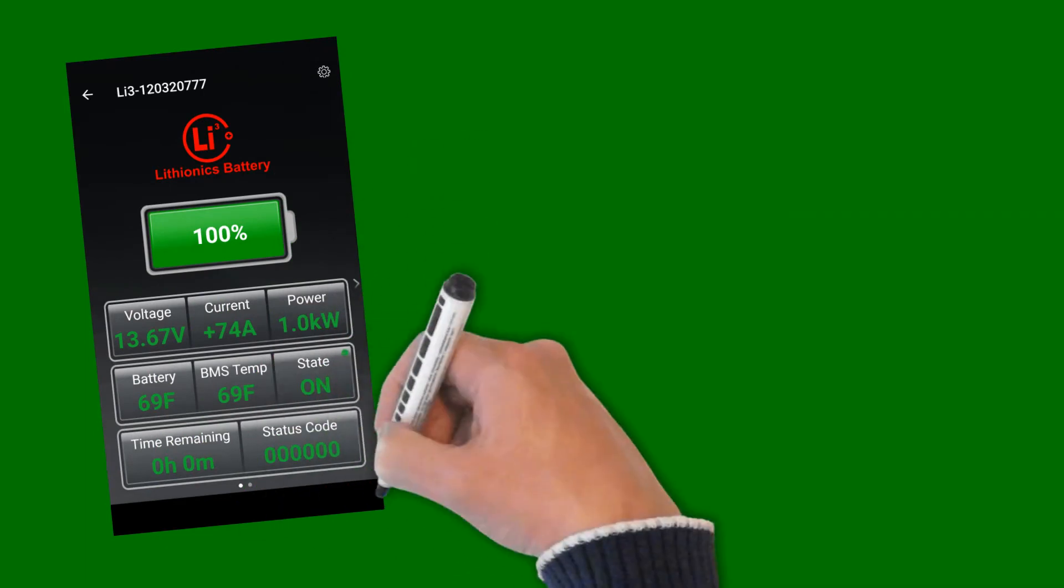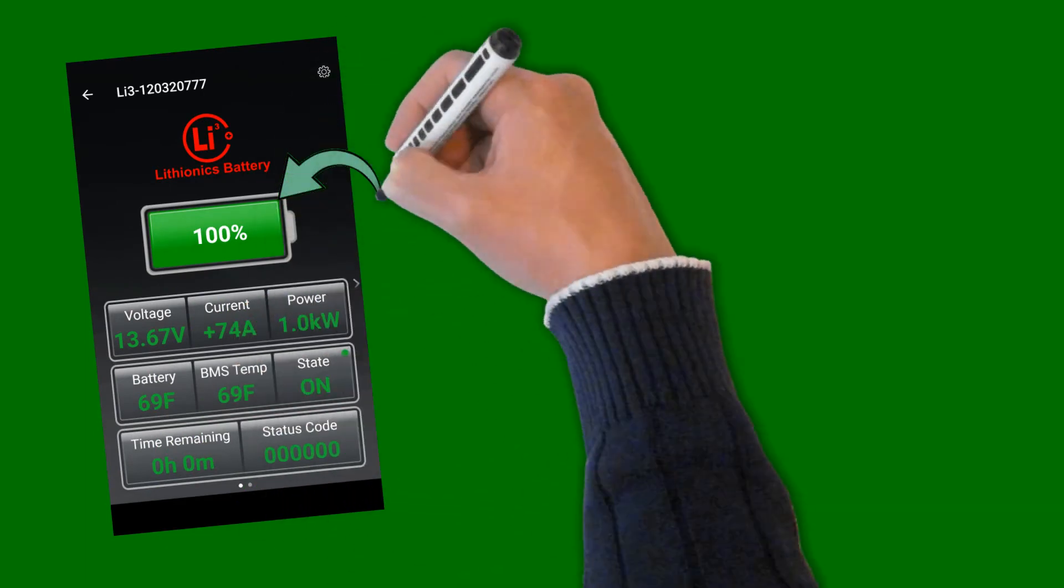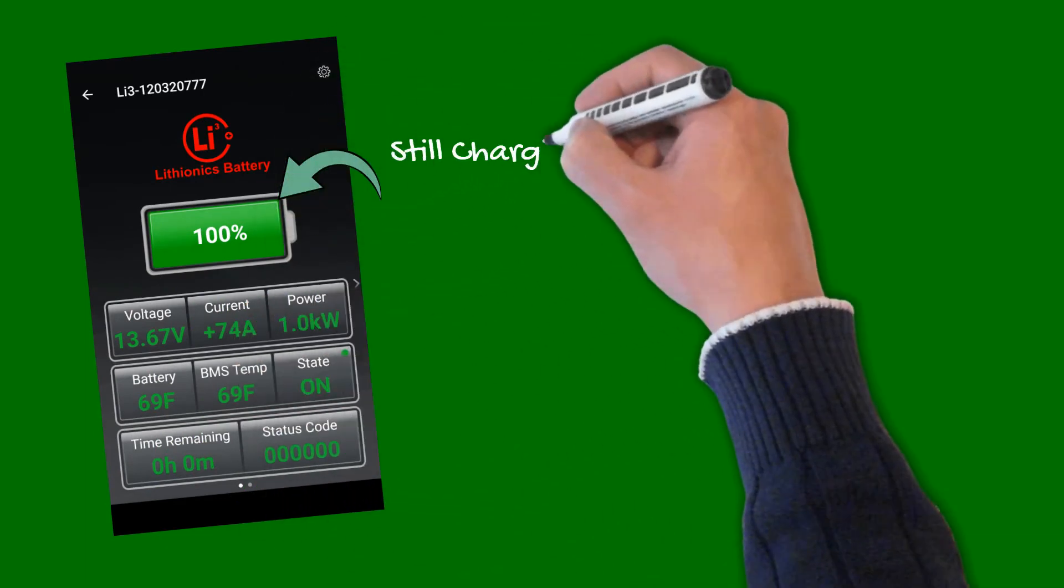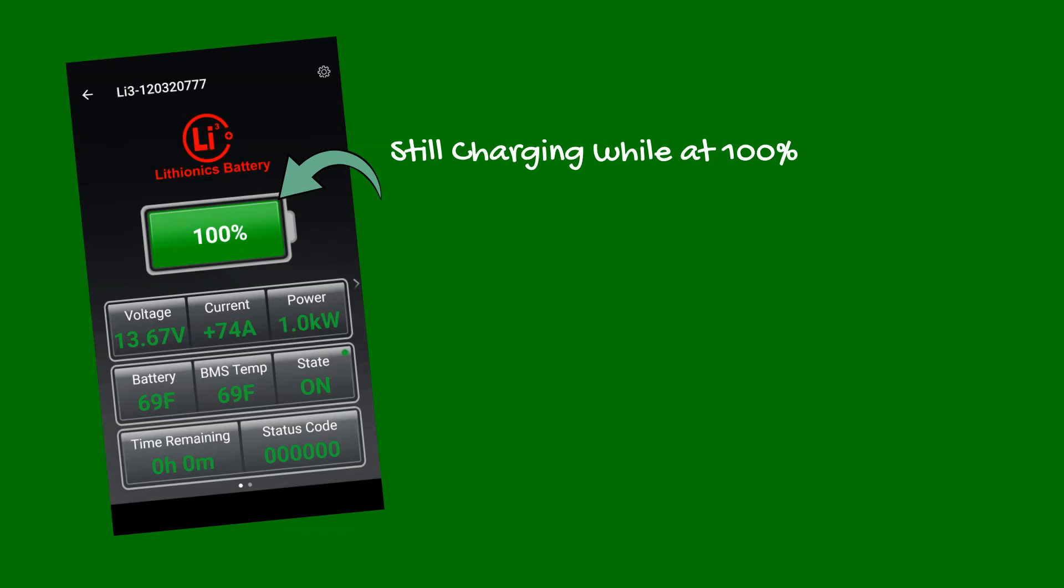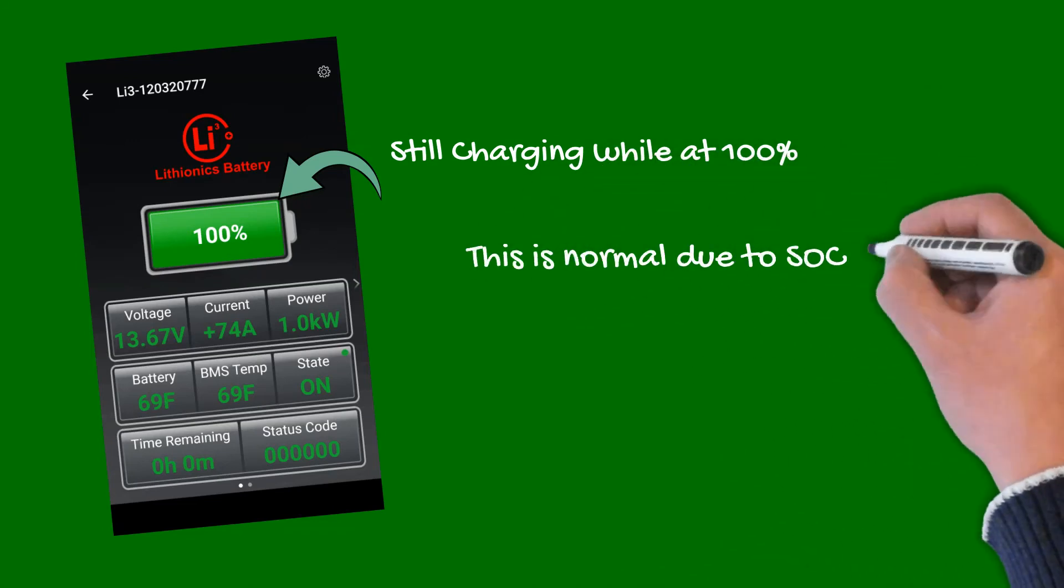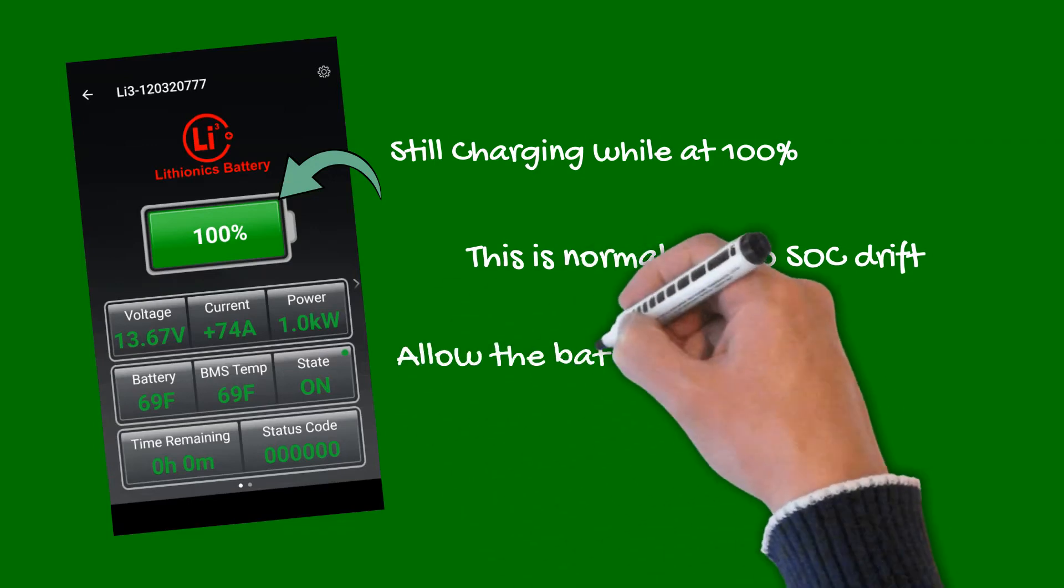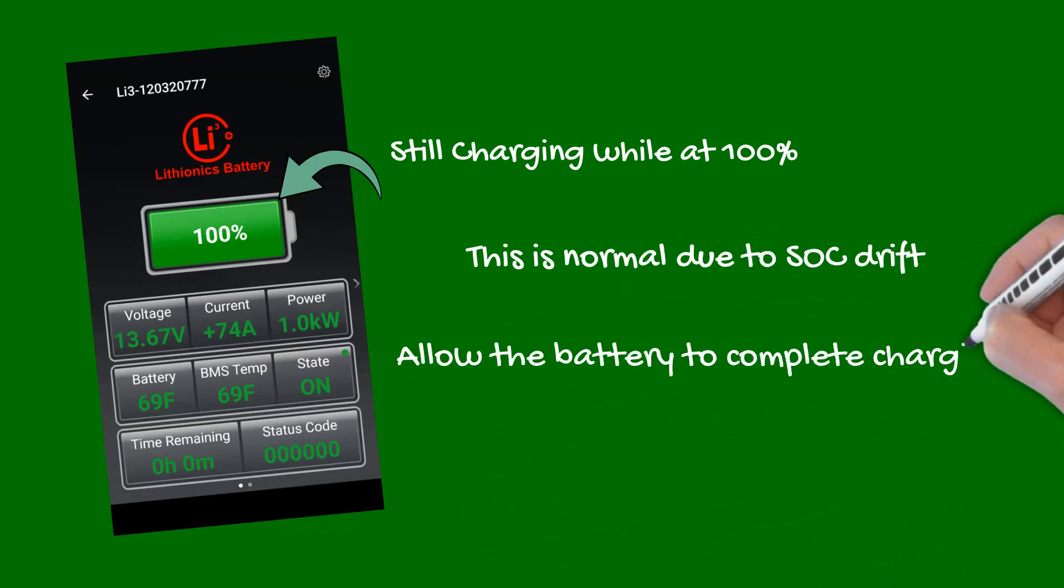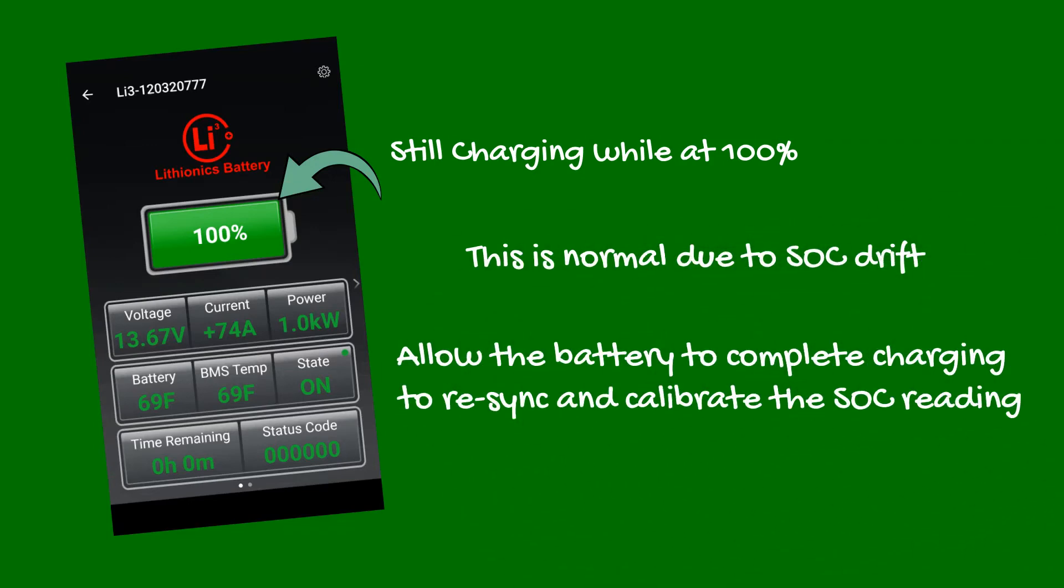At times, you may notice your Lithionics battery is still charging even though the state of charge is already at 100%. This is normal, and related to a slight drift of estimated state of charge. Always allow the battery to finish recharging to re-sync the 100% value with the actual state of charge of the battery.